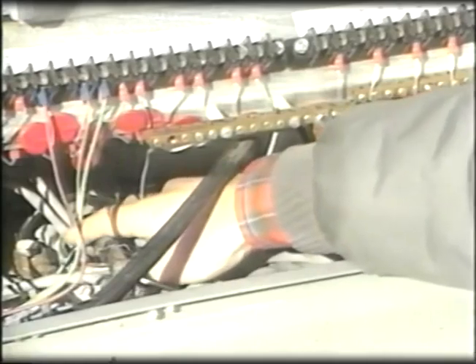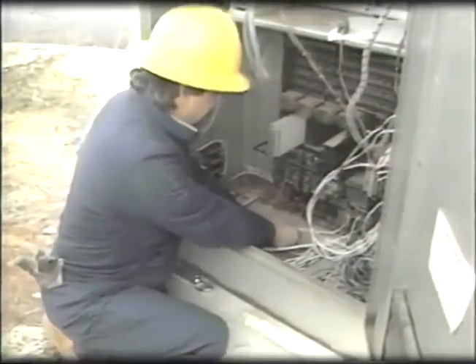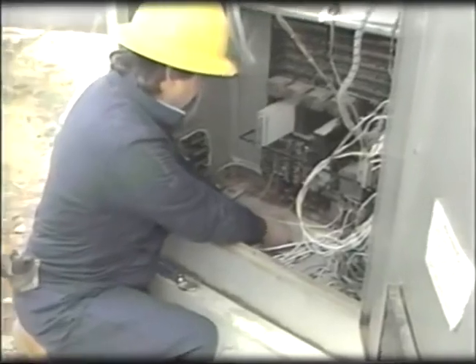In fact, you need to make sure that the electrical ground wire, or green wire with AC service, and the ground rod are interconnected through the controller cabinet. Ground rods provide the necessary path to earth for lightning and fault current. The path from the ground rod to the cabinet must have low impedance, so make the connection between the ground rod and the cabinet with the shortest possible length of wire. We recommend a copper-clad bare wire, number 6 gauge or heavier.